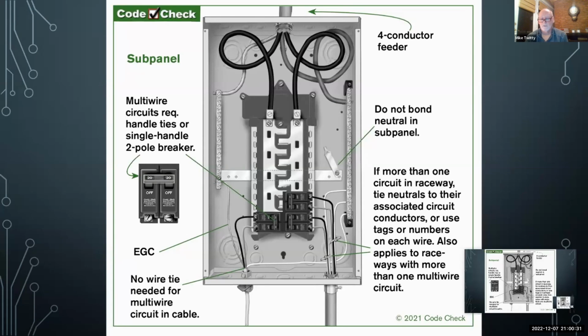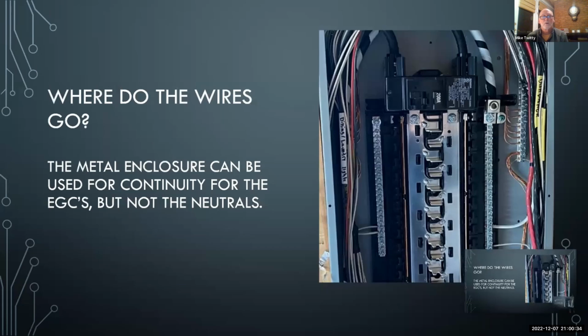I think I've got another slide. I want to discuss something on this same subject here. Okay. Where do the wires go? This is a picture of actually a compliance inspection I did last week, a brand new installation. And I was looking for one of these to kind of get this point across. The metal enclosure can be used for continuity for the equipment grounding conductors, but not for the neutrals. And what that means is this bar right here is bonded. It's directly contacting the panel, so it's connected to it. This is the main service panel, 3-wire feed. No equipment ground feeder for this because it doesn't need it.